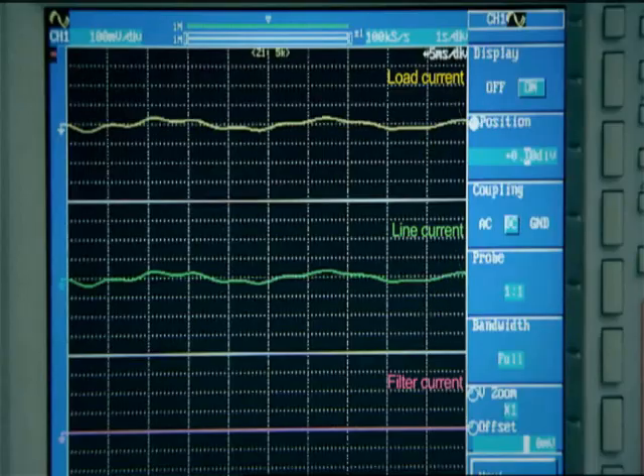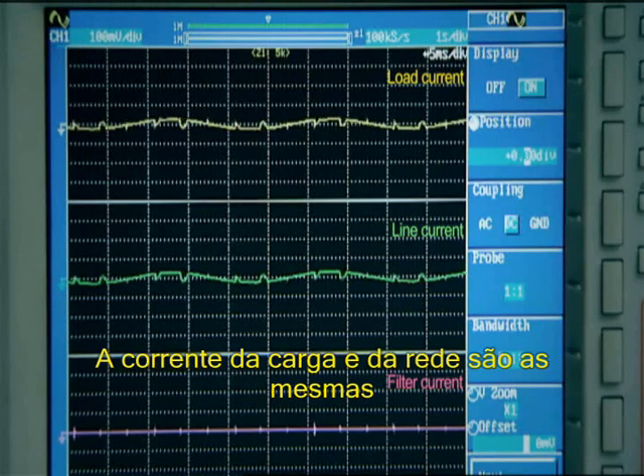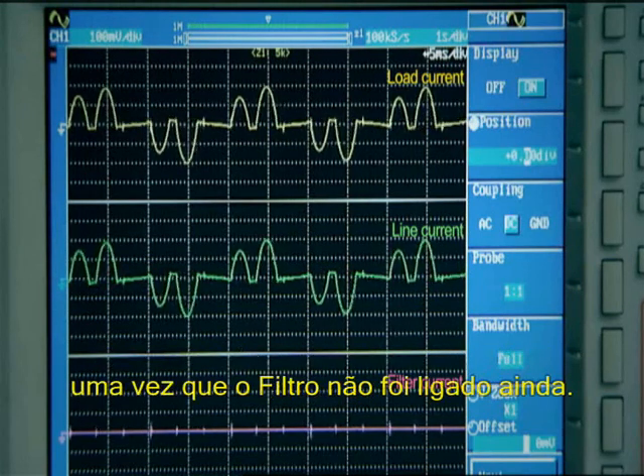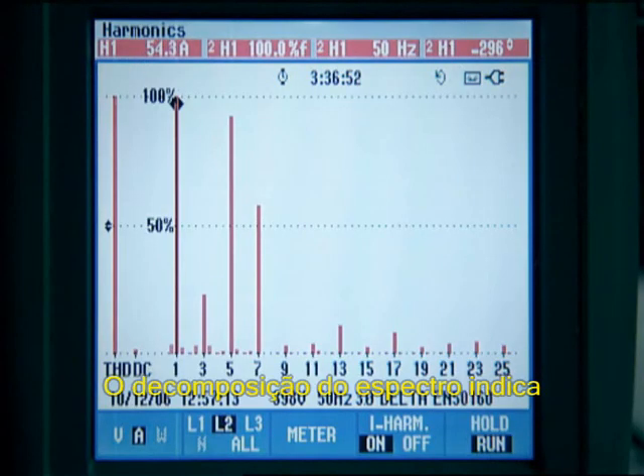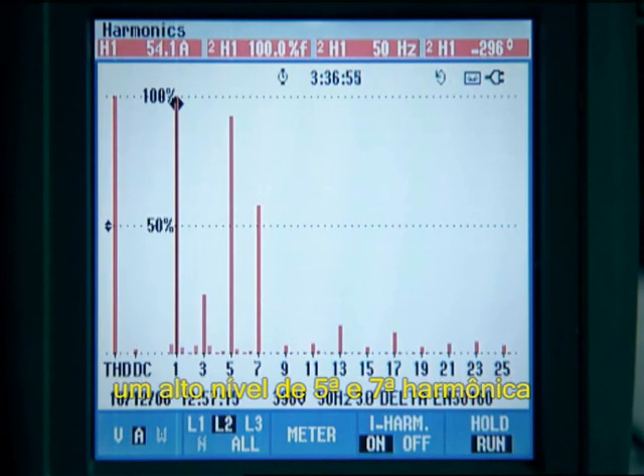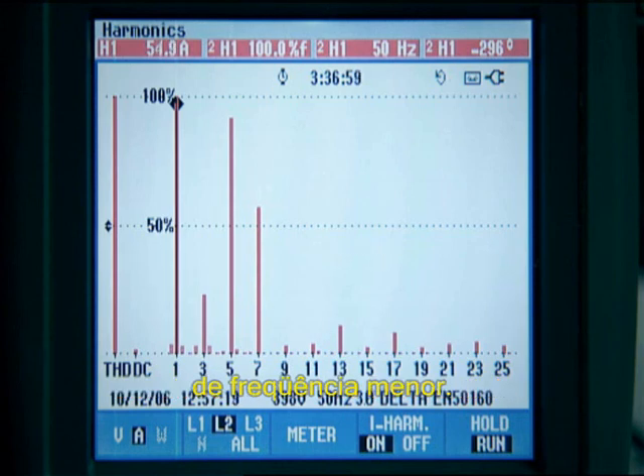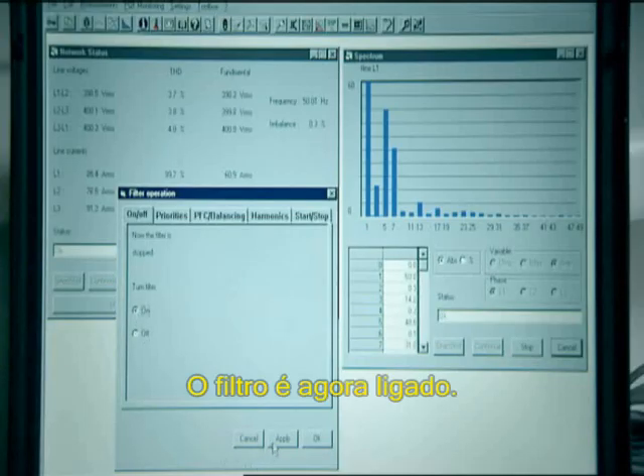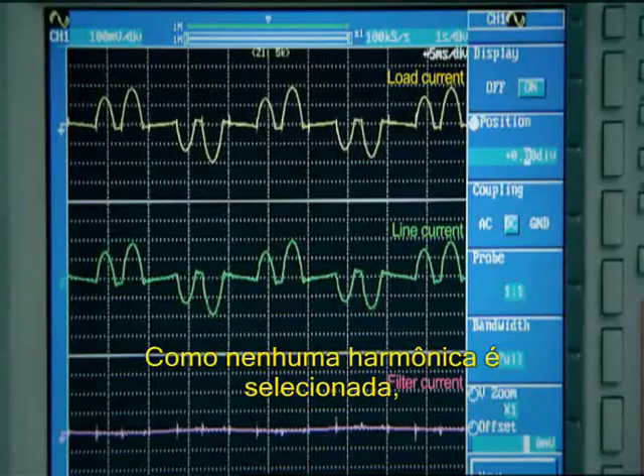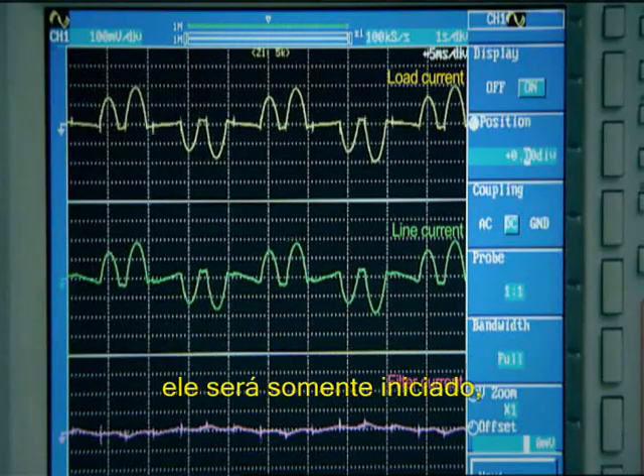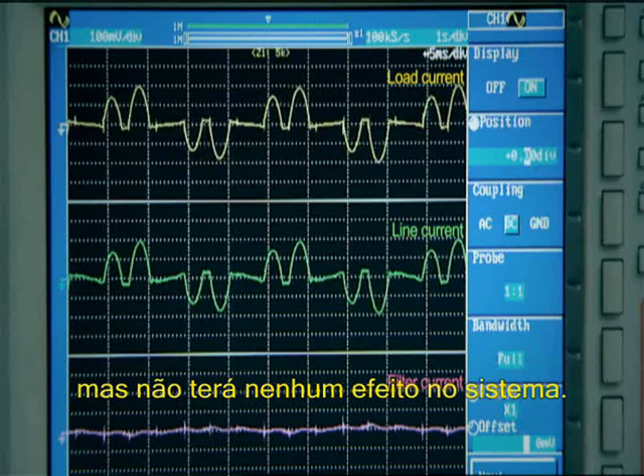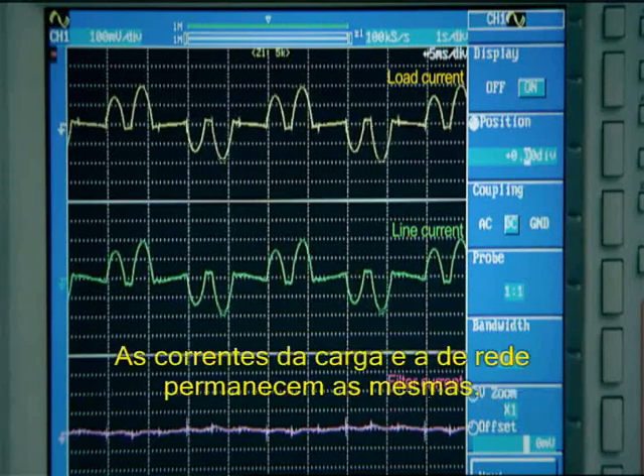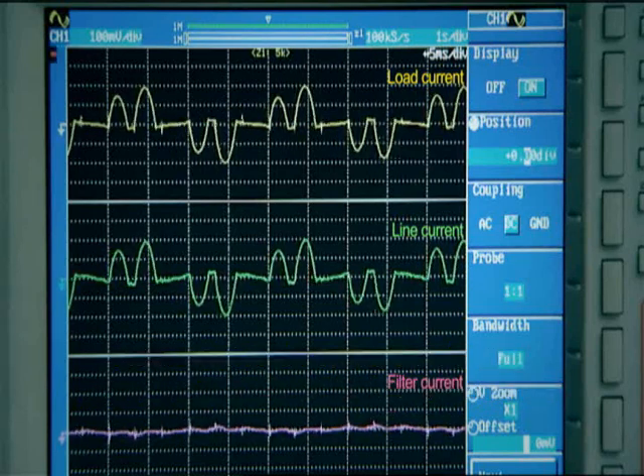First of all, the load is switched on without the filter. The load and the line currents are the same since the filter is not yet switched on. The spectral decomposition indicates a high level of 5th and 7th harmonic, as well as other higher frequency harmonics. The filter is now switched on. As no harmonics are selected, it will just be started up, but will have no effect on the system. The load and line currents remain the same.